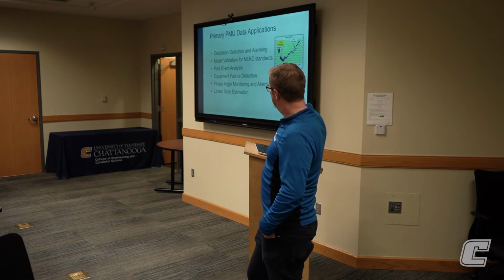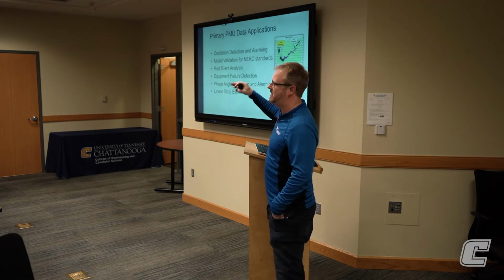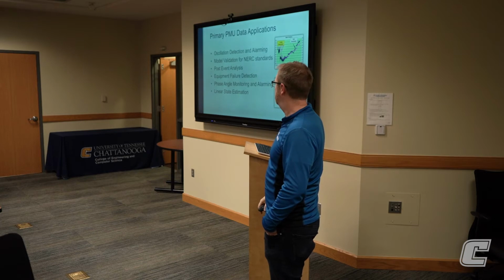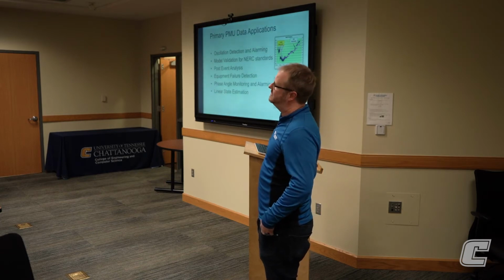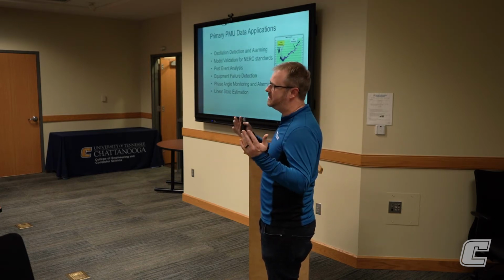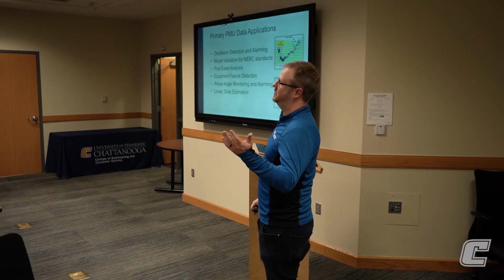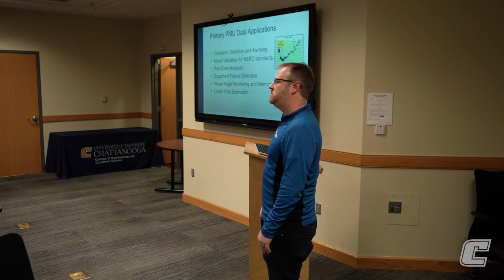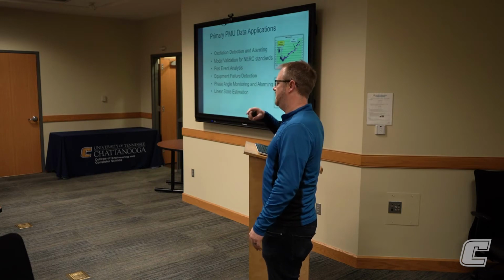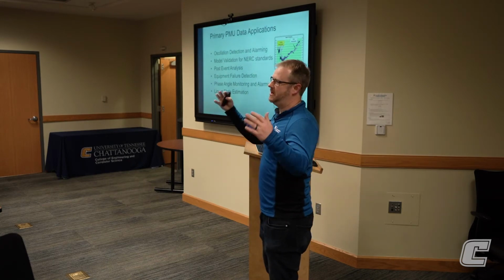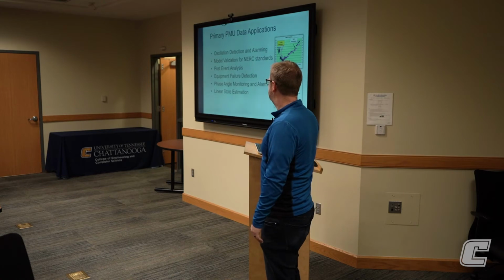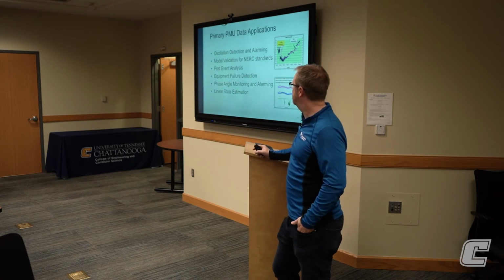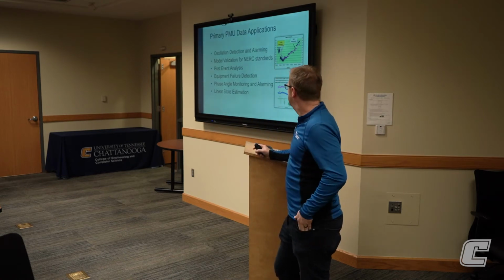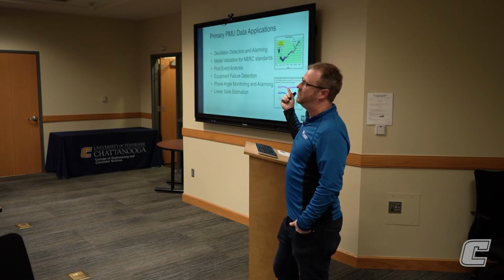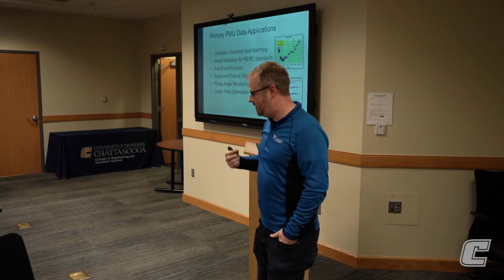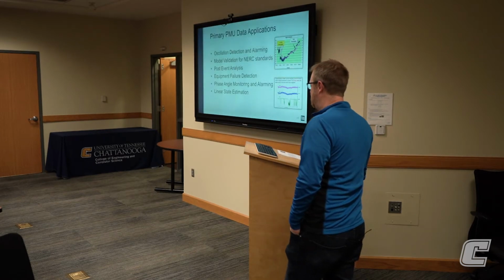We also use it for NERC validation, to show compliance with NERC standards, and for post-event analysis. We've had several storms in the past couple of months, and we've used PMU data to determine that a breaker opened, a substation went dark, giving that level of detail and letting us determine the sequence of events. It would also be great for equipment failure detection, knowing when we're getting ready to have a transformer or something blow up.